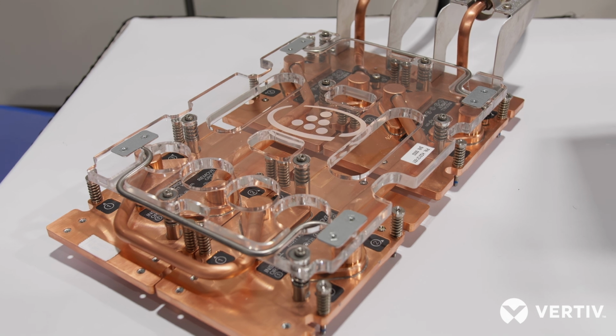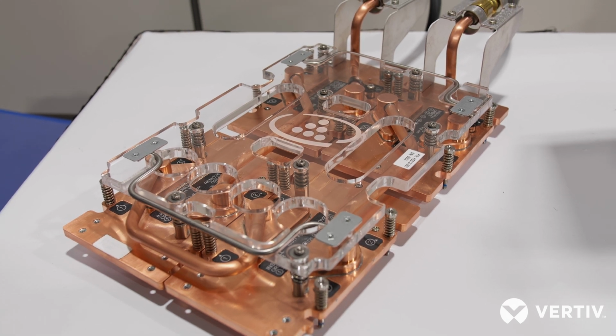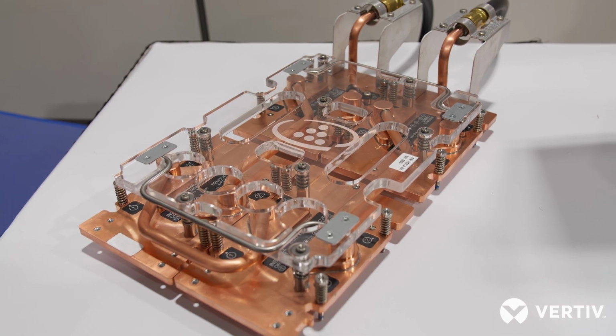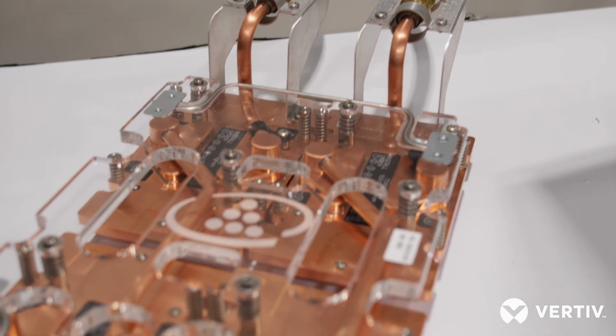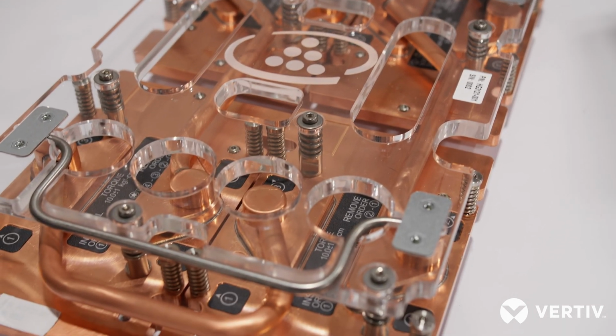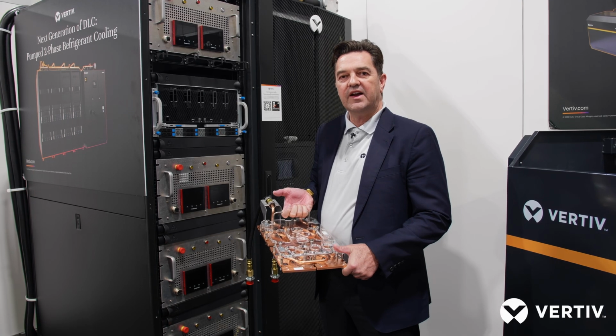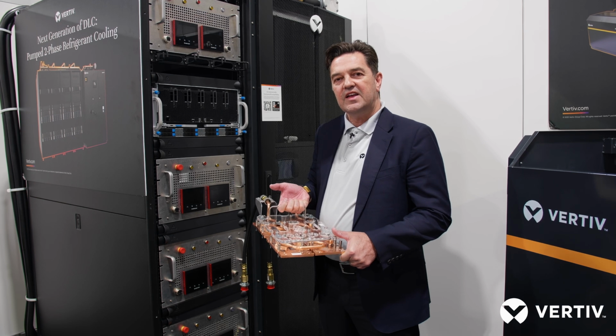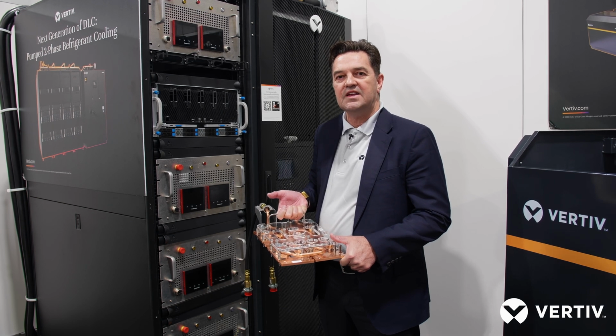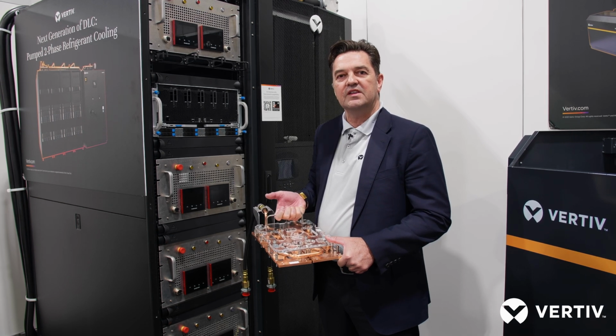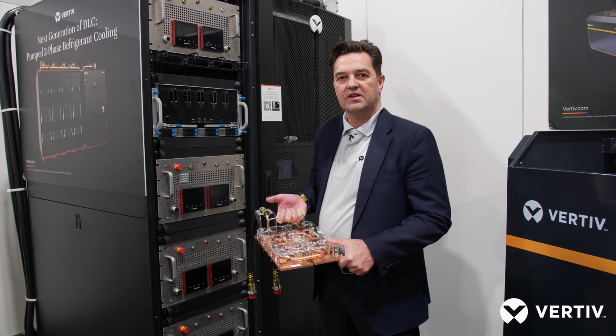To describe that a little closer to you, I'm going to show you the actual accelerator cold plate system that we have here. This cold plate array supports 4 kilowatts of cooling. Attach this into the rack, into the server system, and that facilitates the harvesting of the heat and essentially vaporizing the refrigerant to assist the cooling methodologies.